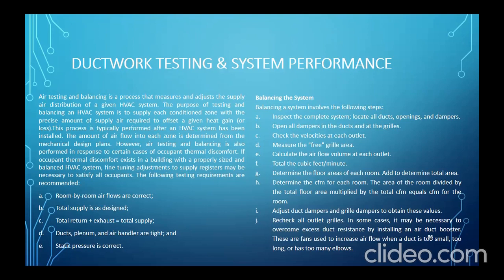However, air testing and balancing is also performed in response to certain cases of occupants' thermal discomfort. If occupant thermal discomfort exists in a building with a properly sized and balanced HVAC system, fine-tuning adjustment to supply registers may be necessary to satisfy all occupants. Okay? Kung nag-design ka ng uniform flow, so sa actual pala, yung sa living room, andun sa isang side yung mga tao, sa iba, daanan lang. So, pwede mo siyang i-adjust with dampers, doon i-concentrate yung hangin. Yung may daanan lang ng tao, wala namang mga tao, hinaan mo.